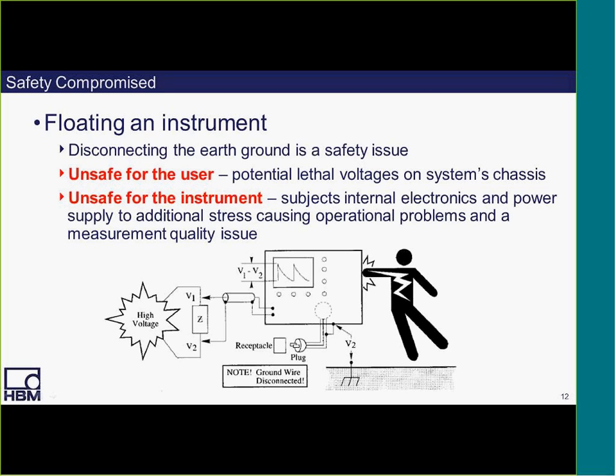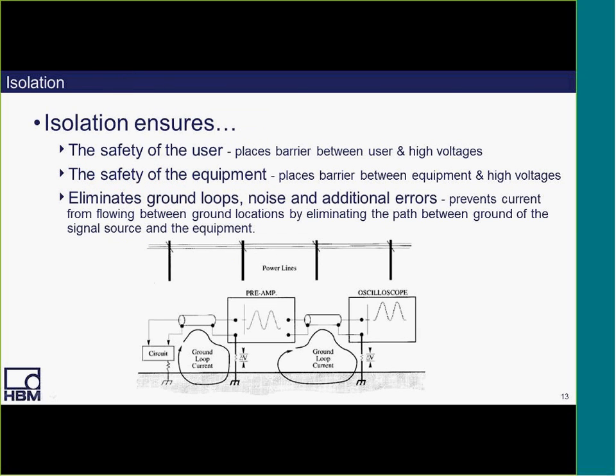Now, unfortunately, this creates a huge safety issue. It's unsafe for the user due to the potential lethal voltages on the system's chassis, and it's unsafe for the instrument, which subjects the internal electronics and power supply to additional stress, causing operational problems and measurement quality issues. So what is the solution? Well, the solution is to use isolation, because the safety of the user is going to be ensured, because the isolation places a barrier between the user and the high voltage. Pretty much the same thing for the equipment.